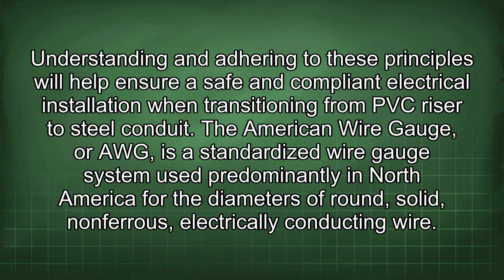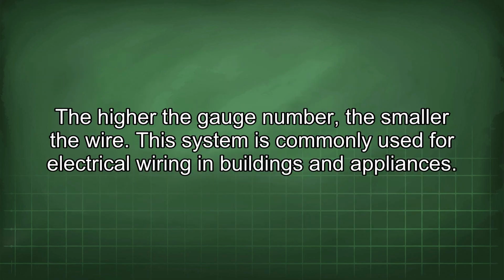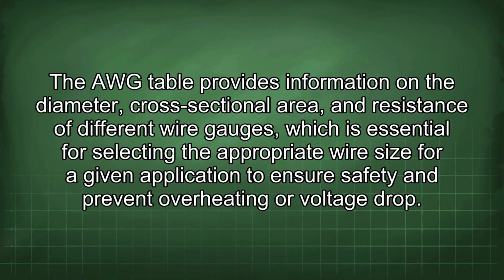to steel conduit. The American Wire Gauge, or AWG, is a standardized wire gauge system used predominantly in North America for the diameters of round, solid, non-ferrous, electrically conducting wire. The higher the gauge number, the smaller the wire. This system is commonly used for electrical wiring in buildings and appliances. The AWG table provides information on the diameter, cross-sectional area, and resistance of different wire gauges, which is essential for selecting the appropriate wire size for a given application to ensure safety and prevent overheating or voltage drop.